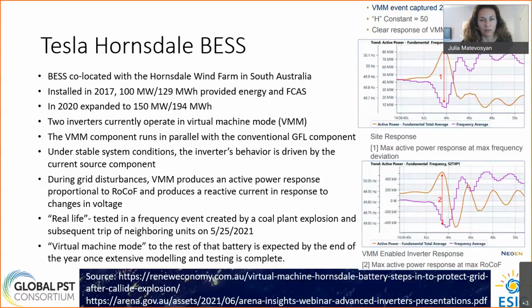You can see that the response starts after frequency starts dropping, and the peak of response is reached at the same time as the frequency nadir. Whereas on the lower plot, you can see the response from those two inverters that were operating in virtual machine mode, and you can see that the response is ahead of frequency, and the peak of response is reached even before the nadir. So that's the response of virtual inertia from these two inverters operating in virtual machine mode.